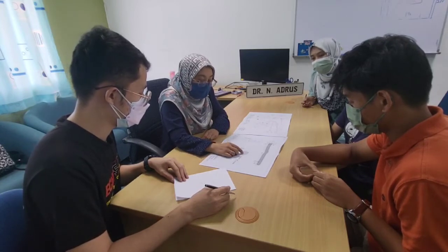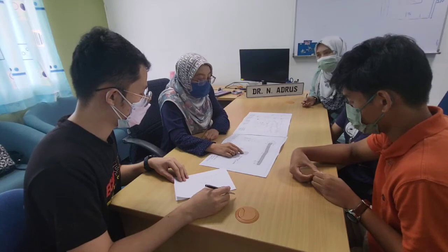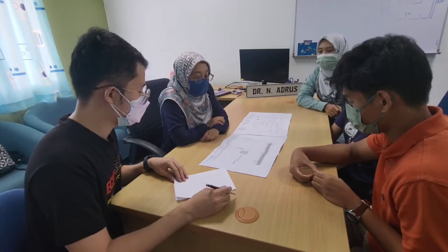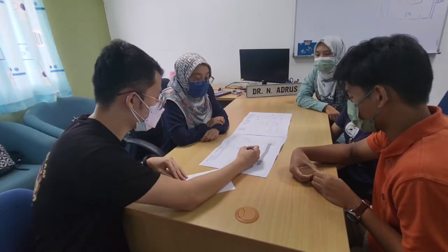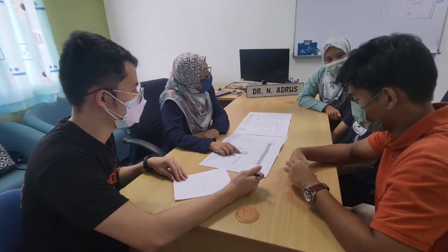Okay. So I think you have improved from the previous calculation, so that's very good as well. And one more thing, is this a triangular or square pitch arrangement of the tubes? It's triangular because you can see that there are many triangles. Okay. So any advantage of triangular compared to the square pitch? Because of space.